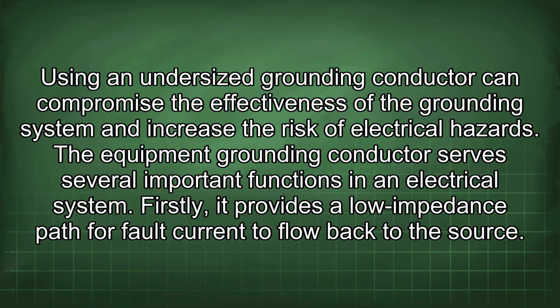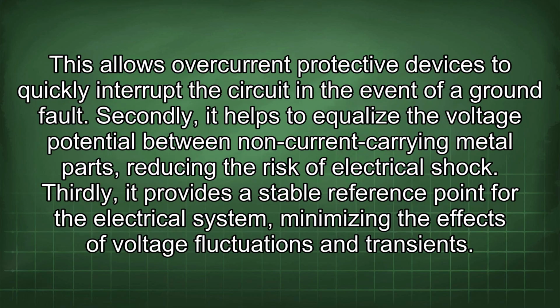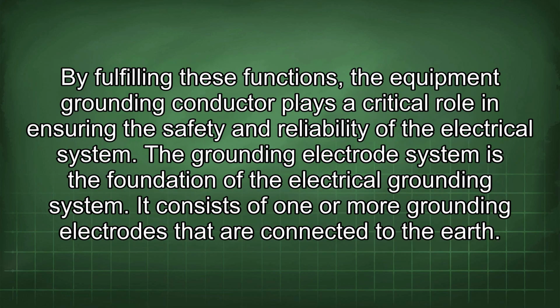The equipment grounding conductor serves several important functions in an electrical system. Firstly, it provides a low impedance path for fault current to flow back to the source. This allows overcurrent protective devices to quickly interrupt the circuit in the event of a ground fault. Secondly, it helps to equalize the voltage potential between non-current carrying metal parts, reducing the risk of electrical shock. Thirdly, it provides a stable reference point for the electrical system, minimizing the effects of voltage fluctuations and transients. By fulfilling these functions, the equipment grounding conductor plays a critical role in ensuring the safety and reliability of the electrical system.